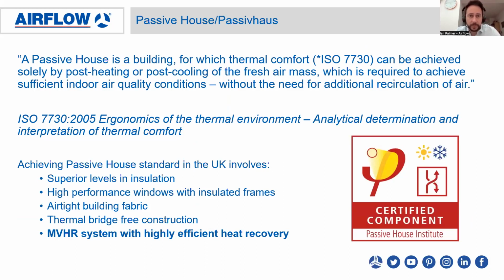Passive house. So Passive House has two spellings there. We've got the British spelling and we've got the European spelling. Passive house is a building for which thermal comfort can be achieved solely by post-heating or post-cooling of the fresh air mass, which is required to achieve sufficient indoor air quality conditions without the need for additional recirculation of air. Typically in the UK, to achieve Passive House standard, you need to have superior levels of insulation, high performance windows with insulated frames, airtight building fabric, thermal bridge-free construction, and very importantly, an MVHR system, so a mechanical ventilation system with highly efficient heat recovery.